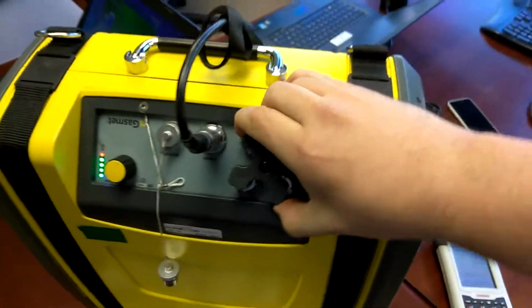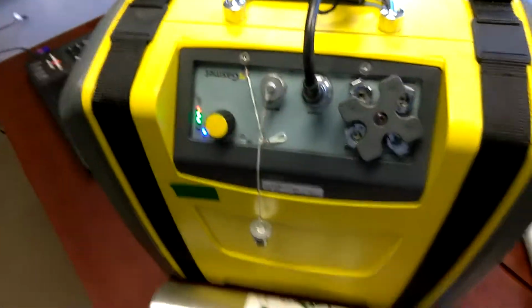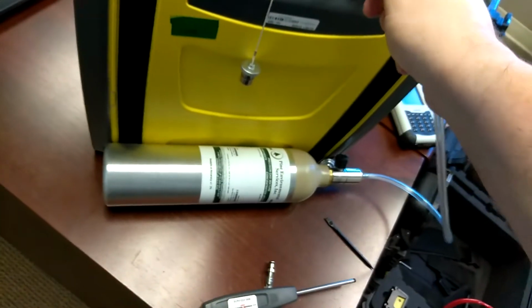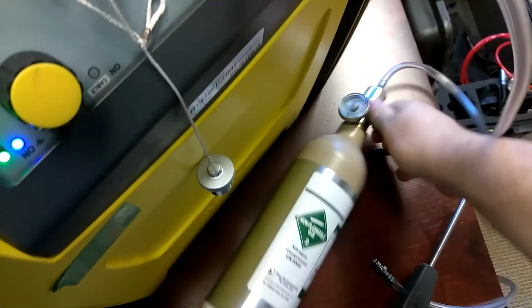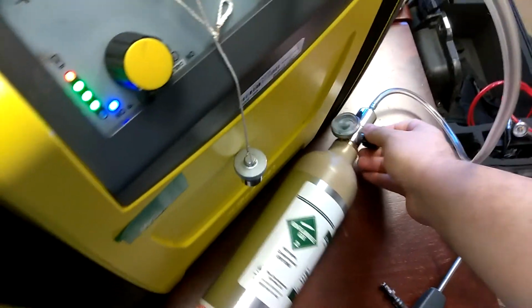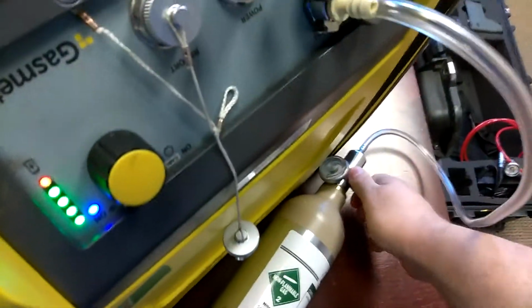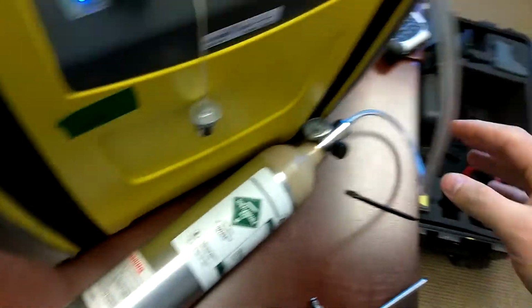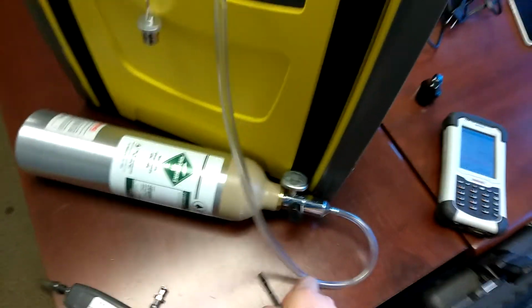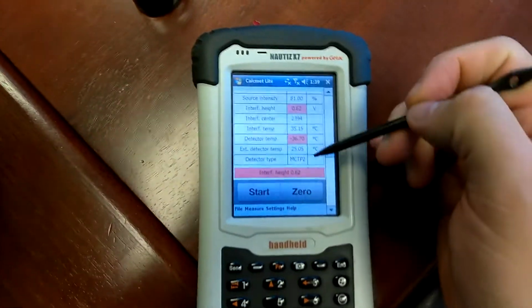In order to do that, you'll come up here to the rotary valve and open that. There's not much pressure on that. It shouldn't give you much resistance. Go ahead and connect your nitrogen zero air to the nitrogen bottle to the zero gas port. It's the bottom left over here. It may be the top right to you. And then you can open your nitrogen, make sure that's ready to go, and that it is flowing. So you won't be able to hear anything, unlike with some calibration gas processes. So that's flowing. The next thing we'll do is take our stylus, go over here and hit the zero button.